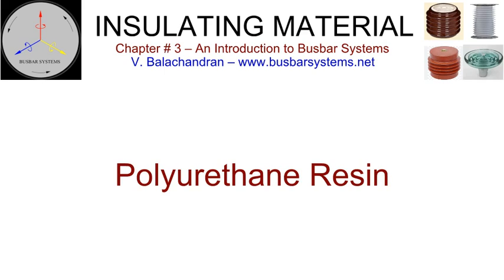Polyurethane resin for potting is commercially available in a liquid state, pre-mixed with a filler element that is quartz or silica. Formulations are available in a two-part process system. The properties of the polyurethane are very similar to that of epoxy resin. It is tough and has better impact resistance. The thermal class of insulation is low and hence, its application is limited.